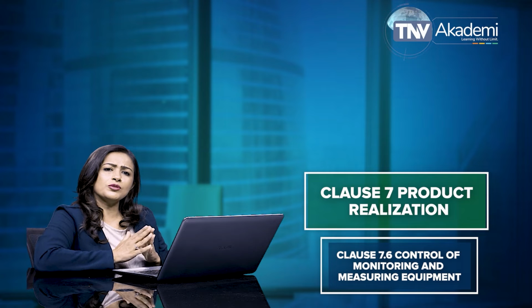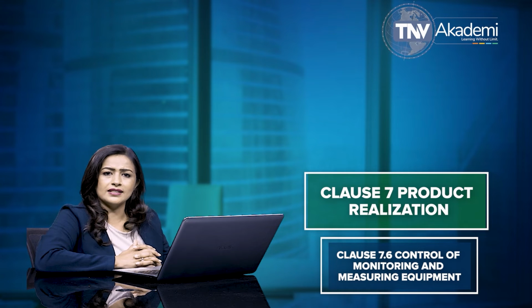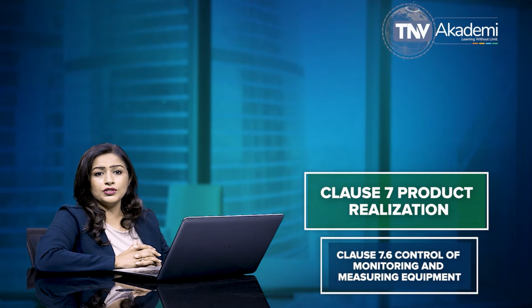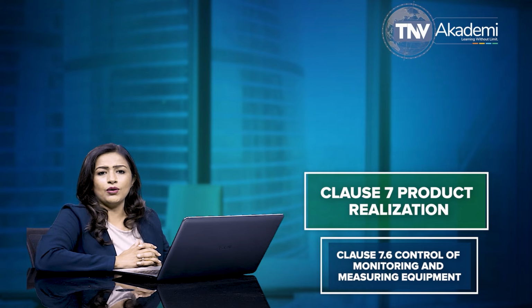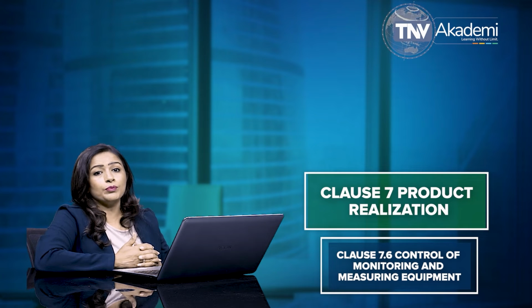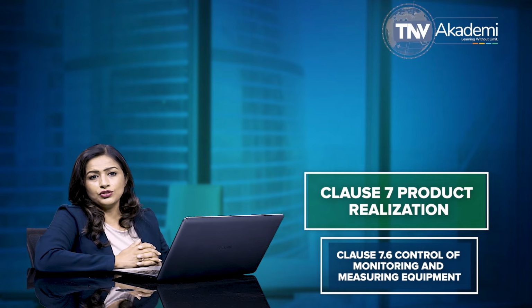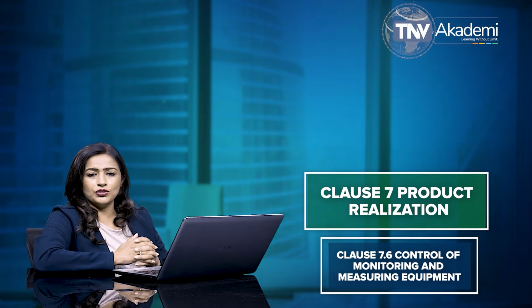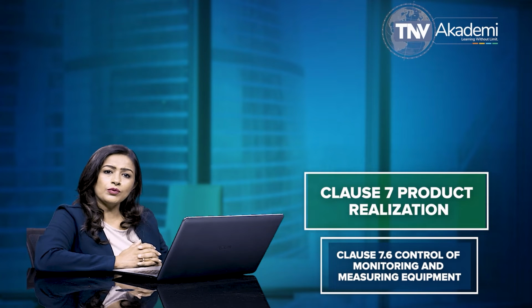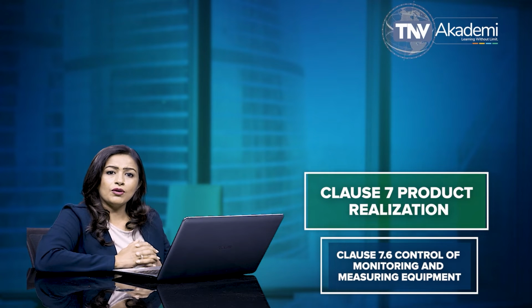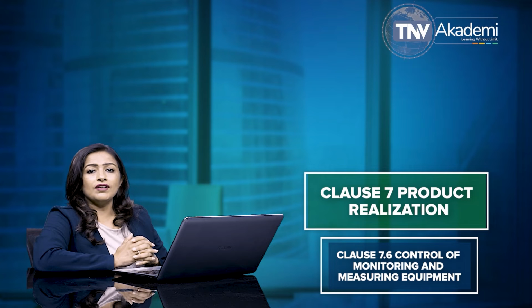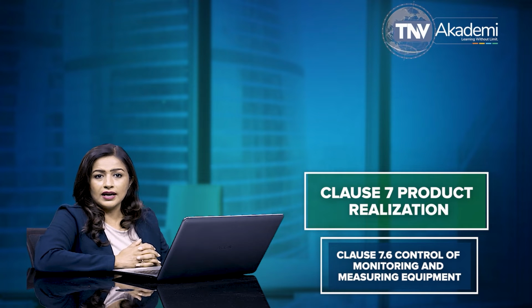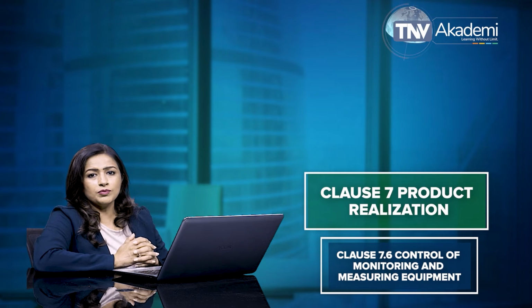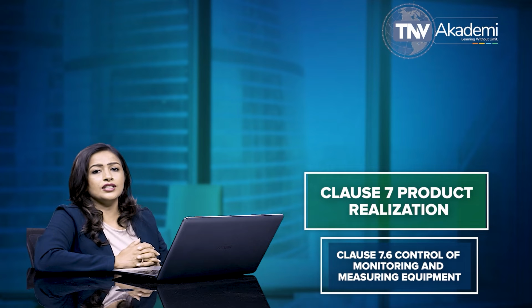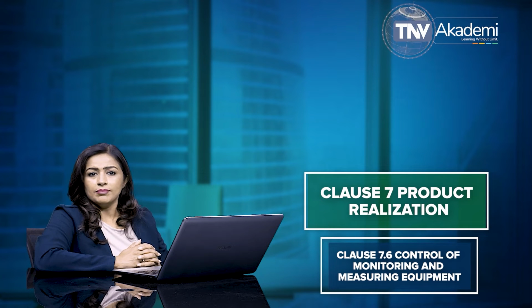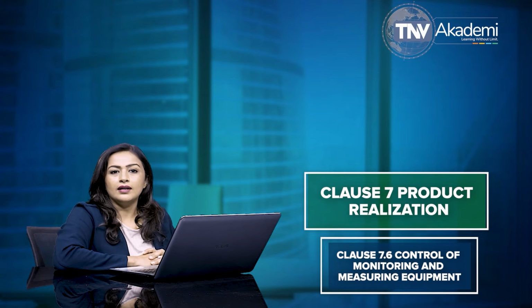Measuring equipment must be adjusted or readjusted as necessary. Such adjustments or readjustments shall be recorded. Measuring equipment must have identification in order to determine its calibration status. Measuring equipment must be safeguarded from adjustments that would invalidate the measurement result, and measuring equipment must be protected from damage and deterioration during handling, maintenance, and storage.